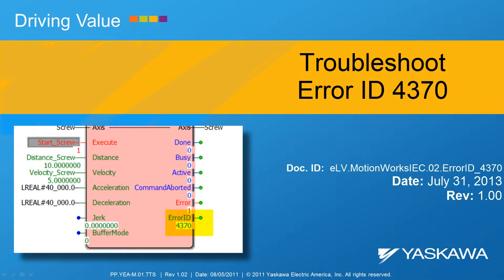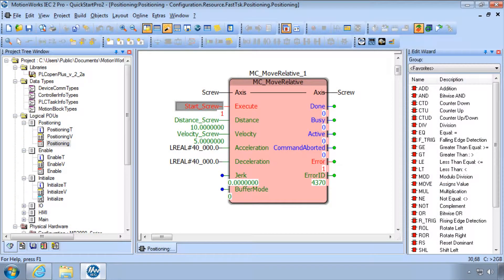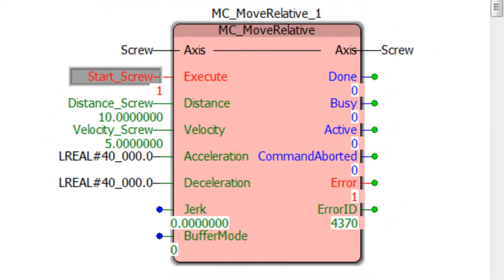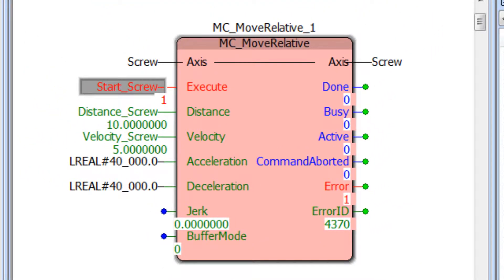This video shows how to troubleshoot and resolve Error ID 4370 on a PLC Open Function block in MotionWorks IEC. Error ID 4370 is most often caused by executing a motion block while the servo is disabled, or an over travel limit switch input is preventing motion.